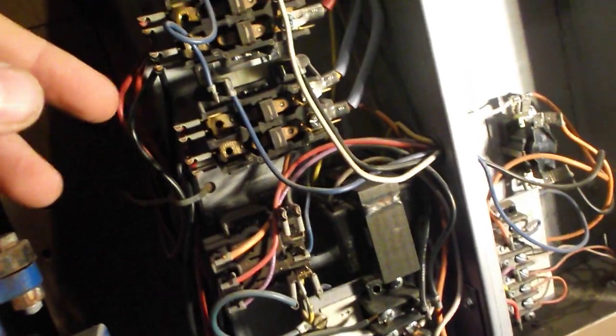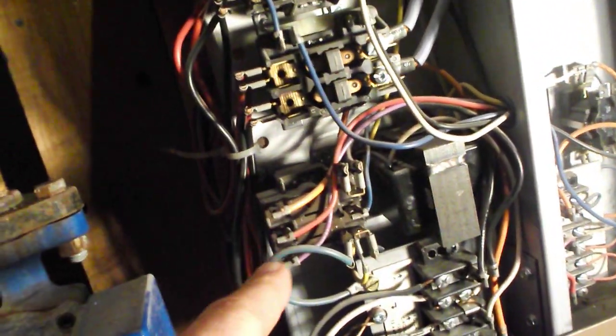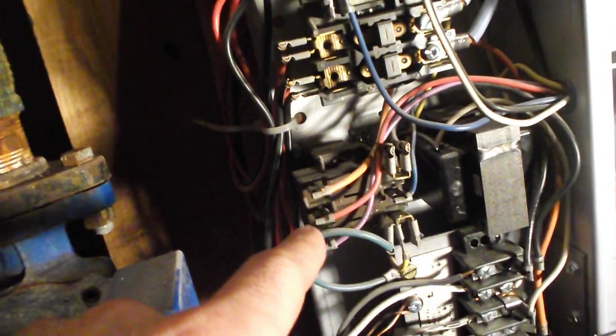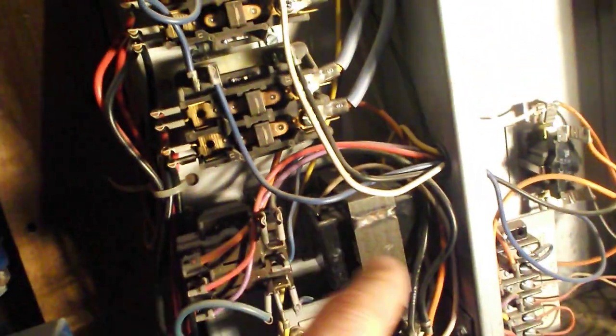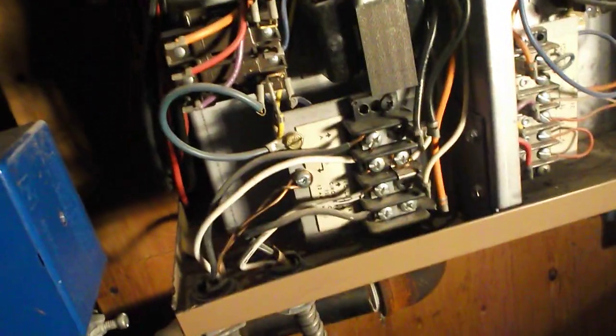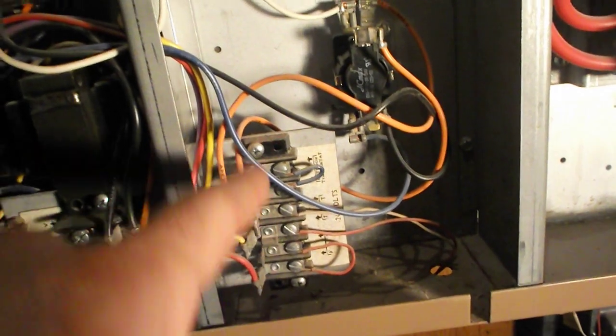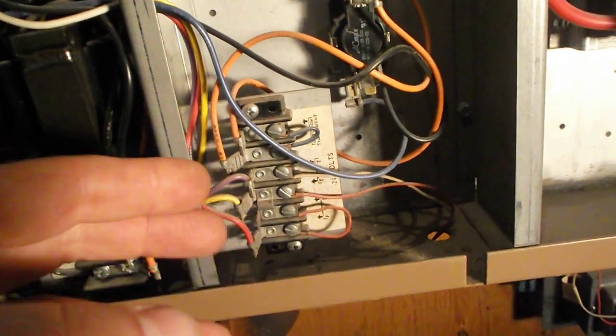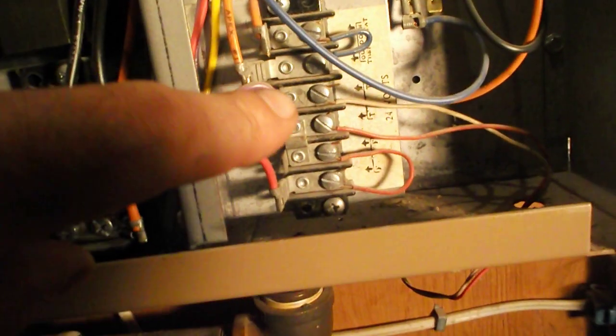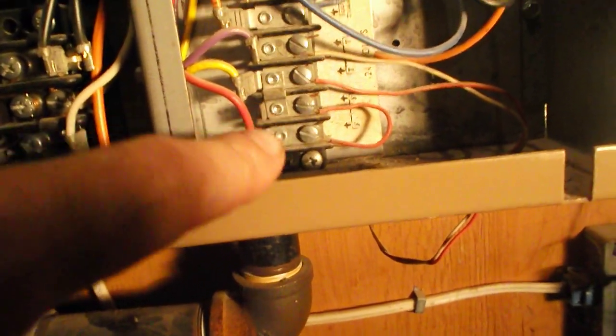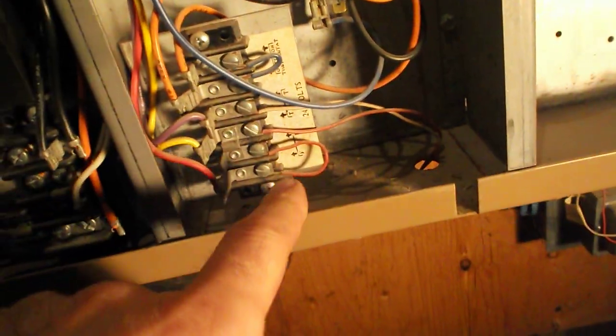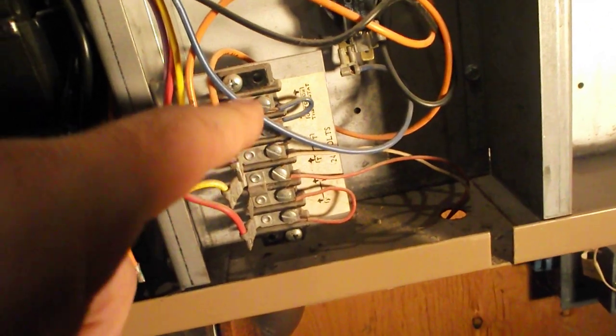The controls for those contactors are down here in this relay assembly. It's a fairly complex relay assembly. And in addition to that, there's a transformer here as well, and then a control panel here as well. And in the middle of the unit, there is this other terminal block. Two leads go out to the thermostat, these two right here. And then these two are looped together. This would be for a flow switch, which we do not use here. It's just jumpered together. And then these other two terminals were for an outdoor thermostat.